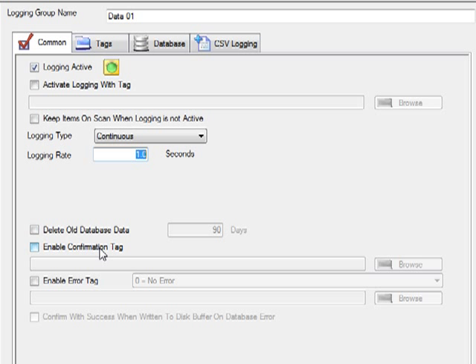One of the most popular properties is the Enable Confirmation Tag to tell the PLC or the device that the record has been successfully logged. Or, if there was an error, we can give it an error feedback as an integer value back to the controller. Those are very popular properties if you're using event-driven logging and want to queue up all of the values in the PLC itself.